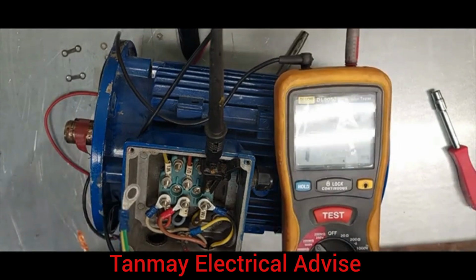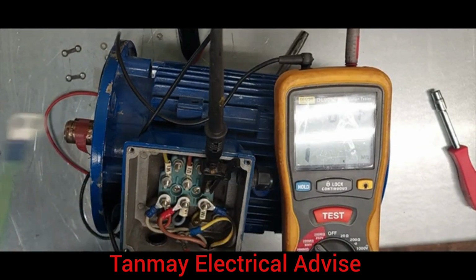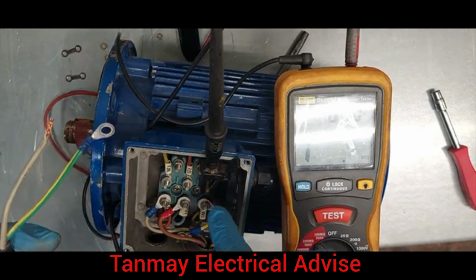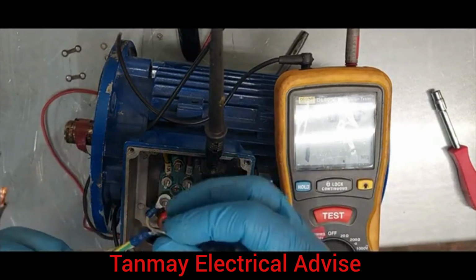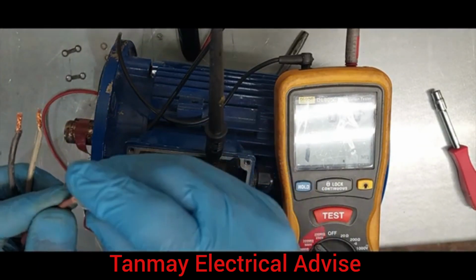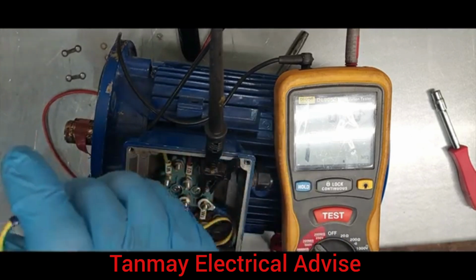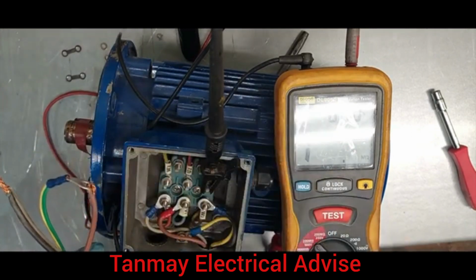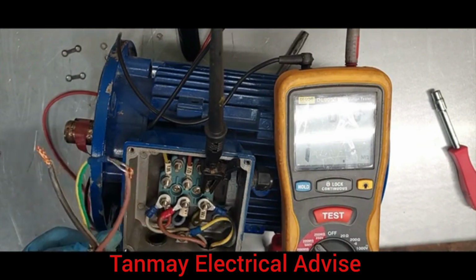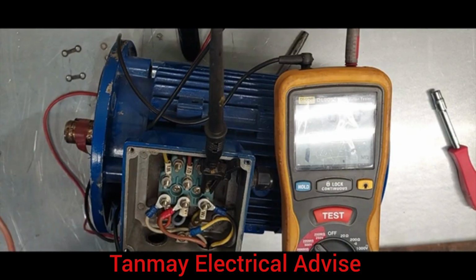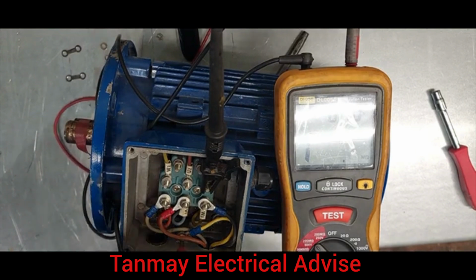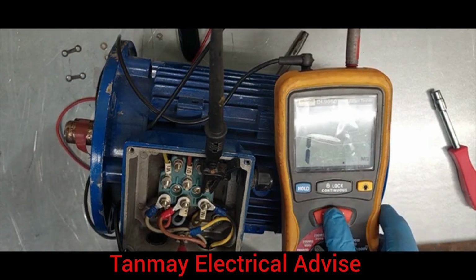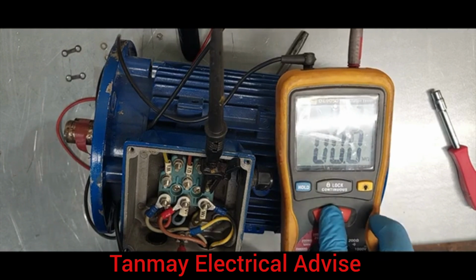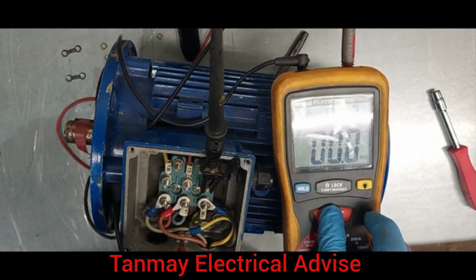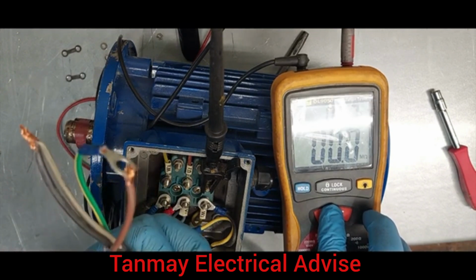Okay, assuming one of the windings is linked to the earth, for example, let us link this one to the earth and see what result we are going to have. Because now we don't have insulation between V1 or V2 and the earth. So let's inject voltage again and see what we come up with. We inject 500 volts on U2 and we can see that now we have 0 mega ohm. This shows that there's no insulation. We can see that it's linked here.